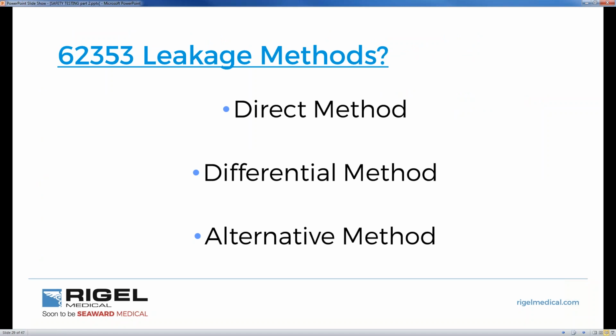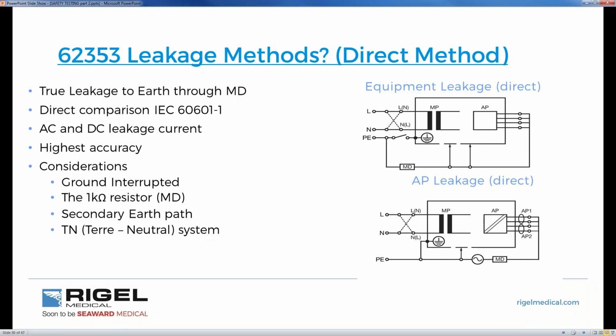So why do we have different methods? What is this confusion between our different leakage methods? Which one does what? How does it do it? Well, we'll go over that one by one. The direct method is the true leakage to earth through the measuring device, and the direct comparison is 60601. So the only difference between the 60601 is we common all of our applied parts to our chassis and our isolated parts on the medical device.